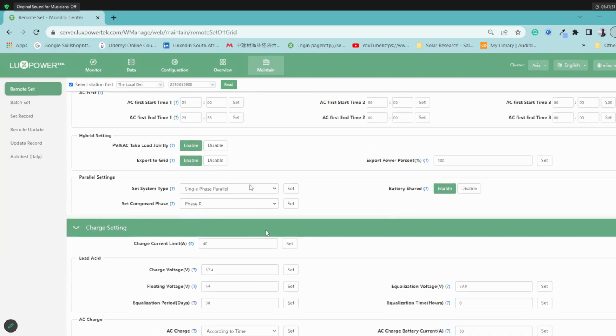Okay, the parallel settings. If you have 2 inverters, you're going to set it to single phase. You can set 3 inverters or 4 or more to single phase. When you set this, you select single phase, click on set, and then you can ignore the phase R over here.